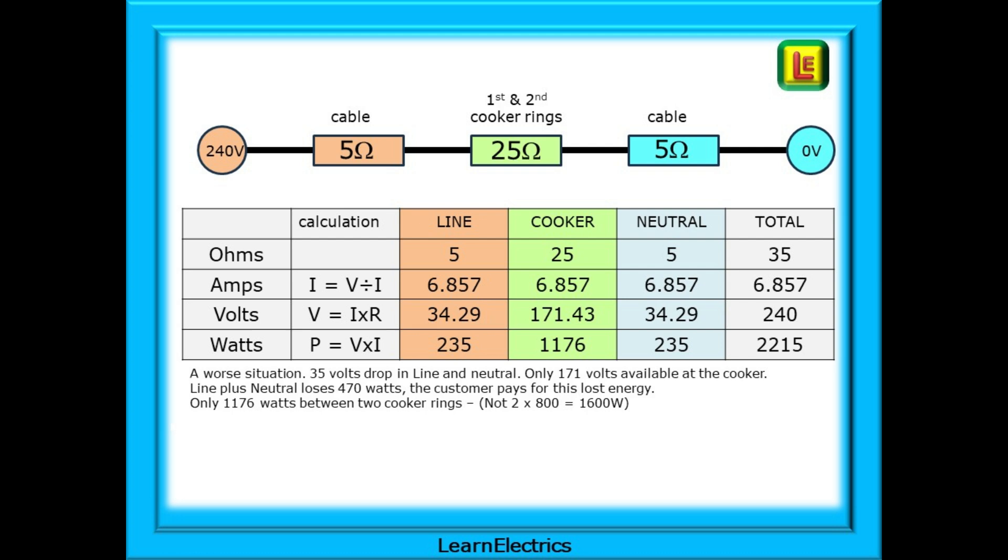The table shows that we have a much worse situation. There is a 35 volt drop in the line and neutral conductors, and only 171 volts is available at the cooker. Line plus neutral loses 470 watts of power, and the customer is paying for this lost energy. Only 1176 watts of power is produced between the two cooker rings. This is not the 2 times 800 watts or 1600 watts that you might expect from the previous example, as each ring is producing less than 600 watts of usable power.